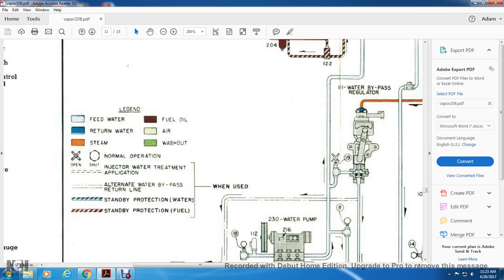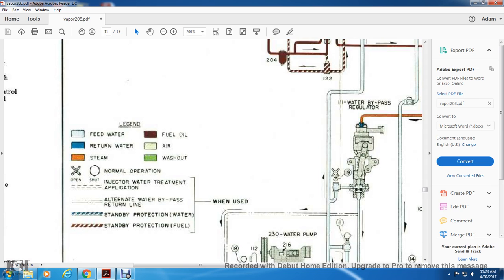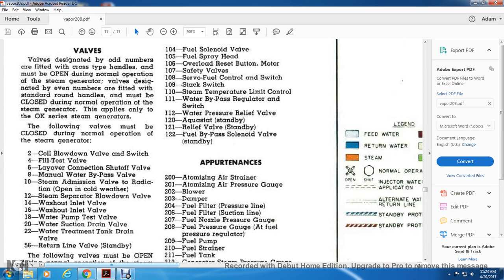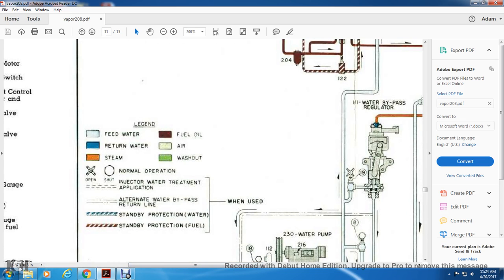Alright, your legend: light blue is feed water, full blue is return water, orange is steam, and brick red is fuel oil, white is air, green is washout. Your cross handle is open, which means it's open during operation, and your round handle is shut for normal operation. The double dash line means injector water treatment application. The smaller dash with a large dash, double dash, is the alternate water bypass return line.